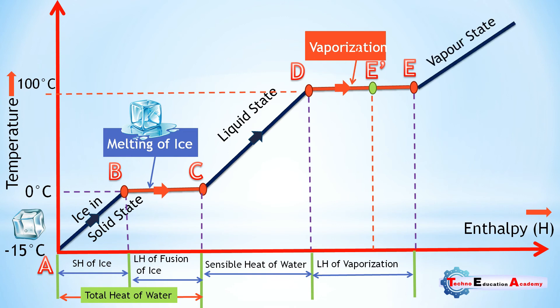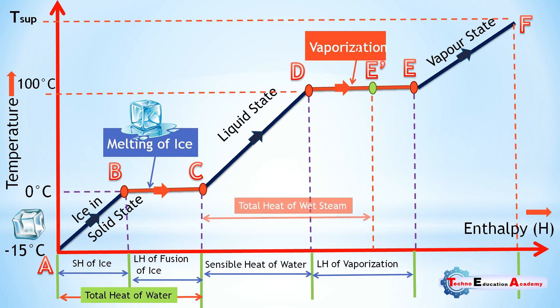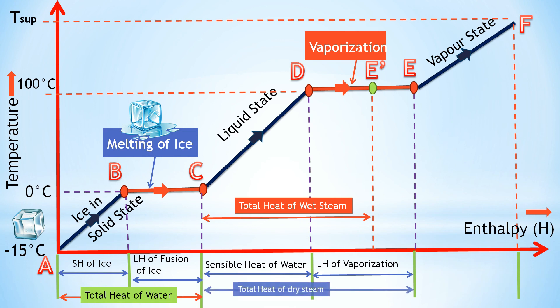Superheated steam is obtained by heating dry saturated steam at constant pressure. In superheated steam there is no moisture content. The process of superheating is shown by line EF on the temperature-enthalpy diagram, and the amount of heat added during this process is called the heat of superheat. The temperature difference between the temperature of superheated steam and that of dry saturated steam is called the degree of superheat — that is, T_superheated minus T_saturated.